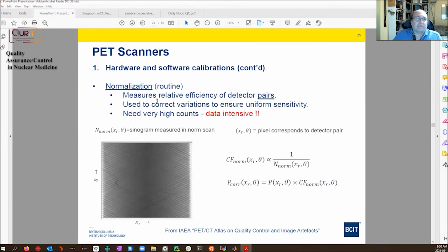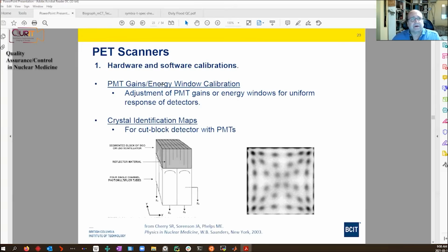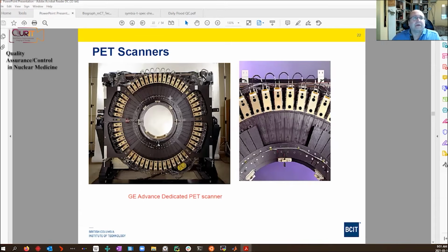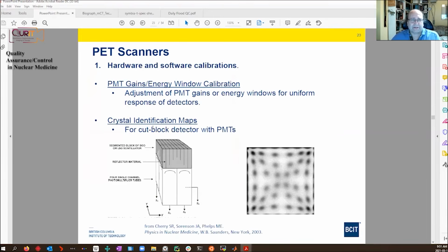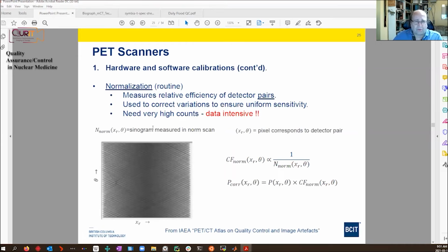Another very important calibration, which could also be considered a routine procedure, is normalization. This is a procedure which measures and comes up with correction factors for the relative efficiency of detector pairs. So again, if we go back here and look at these detectors, if a gamma ray hits here and here, what is the efficiency of this detector pair compared to all the other detector pairs? This needs to be measured to provide a uniform sensitivity within the detector ring. And so this procedure is called the normalization scan.